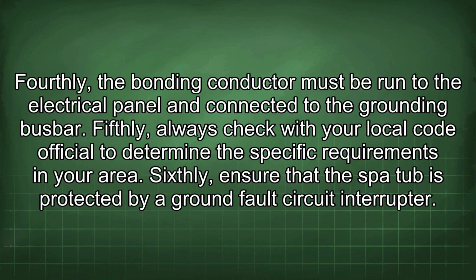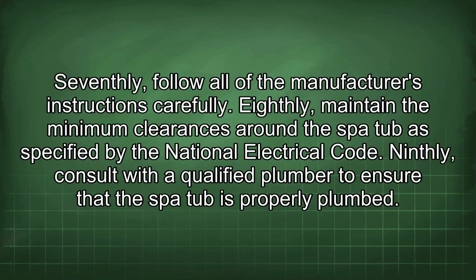Fourthly, the bonding conductor must be run to the electrical panel and connected to the grounding bus bar. Fifthly, always check with your local code official to determine the specific requirements in your area. Sixthly, ensure that the spa tub is protected by a ground fault circuit interrupter. Seventhly, follow all of the manufacturer's instructions carefully.